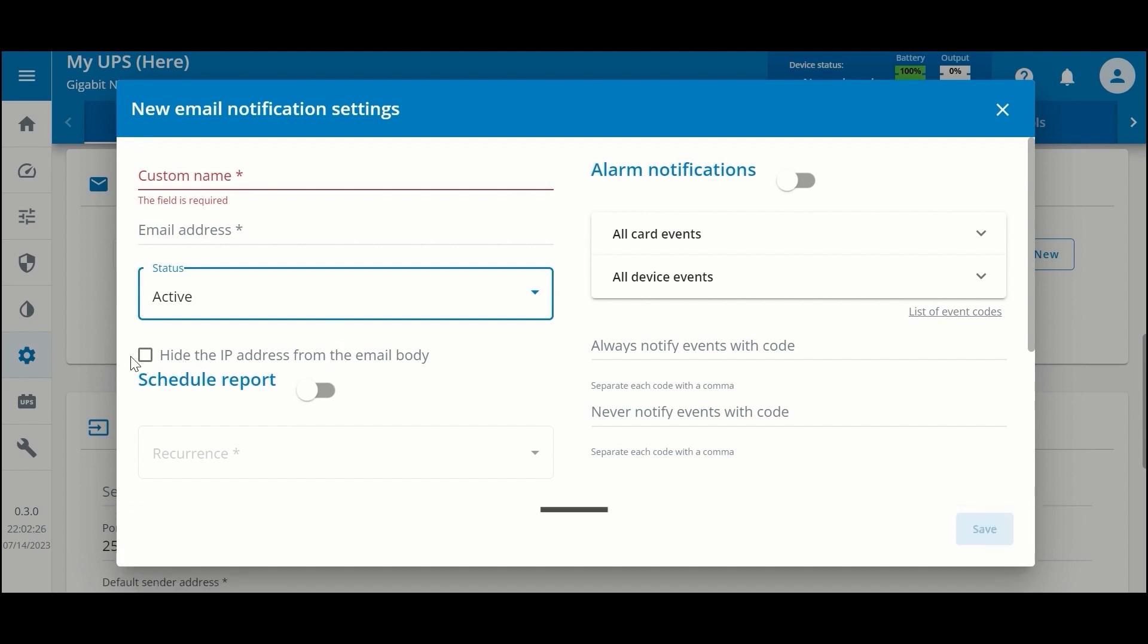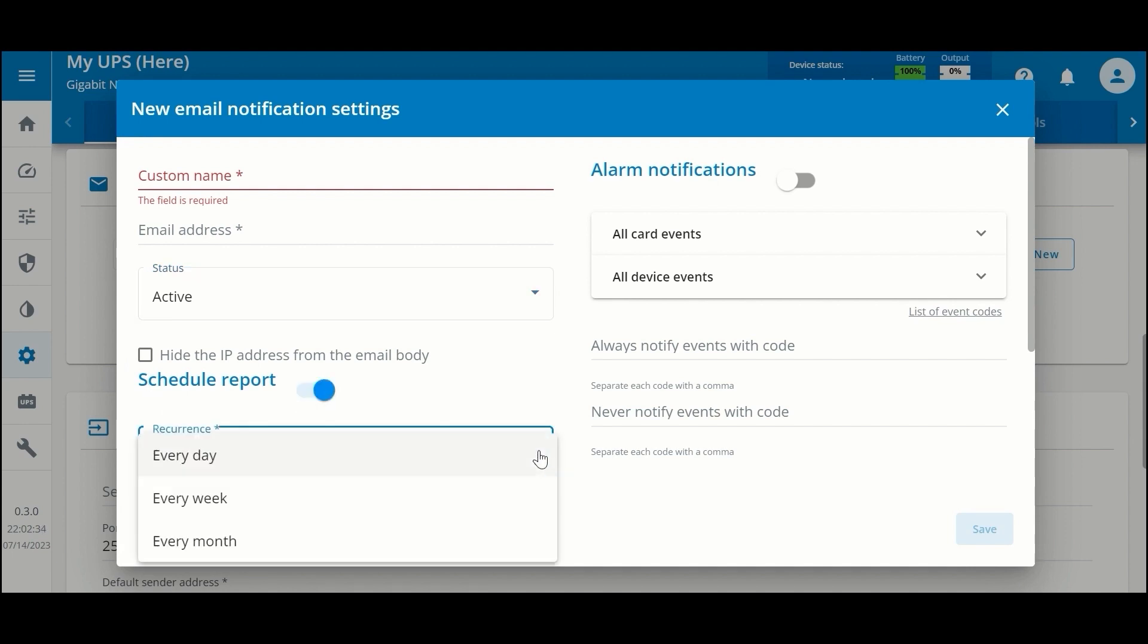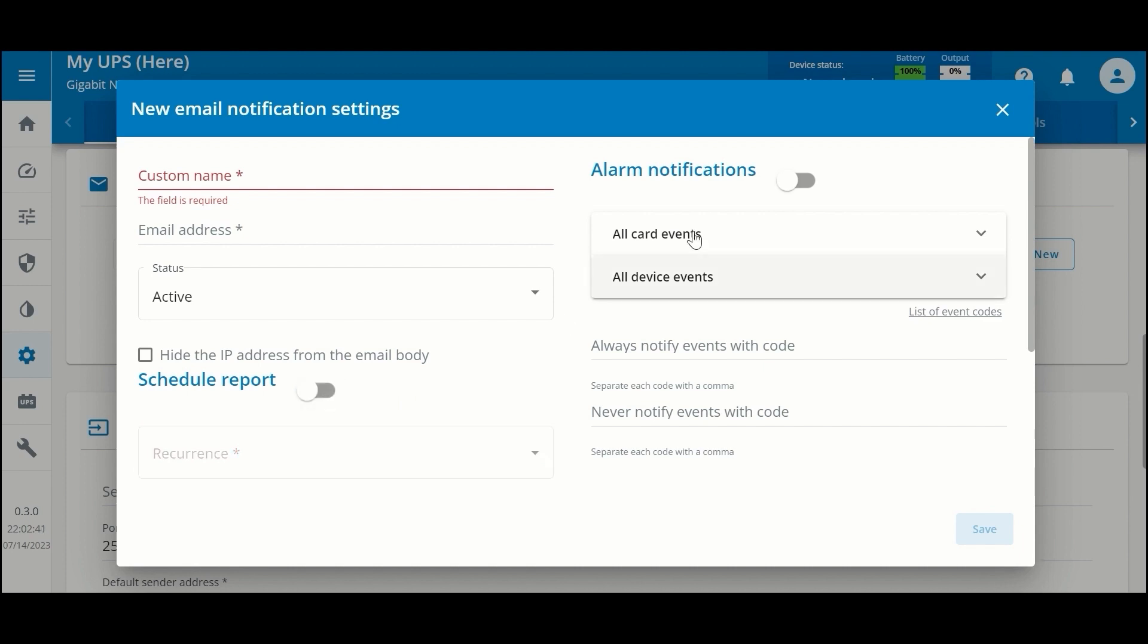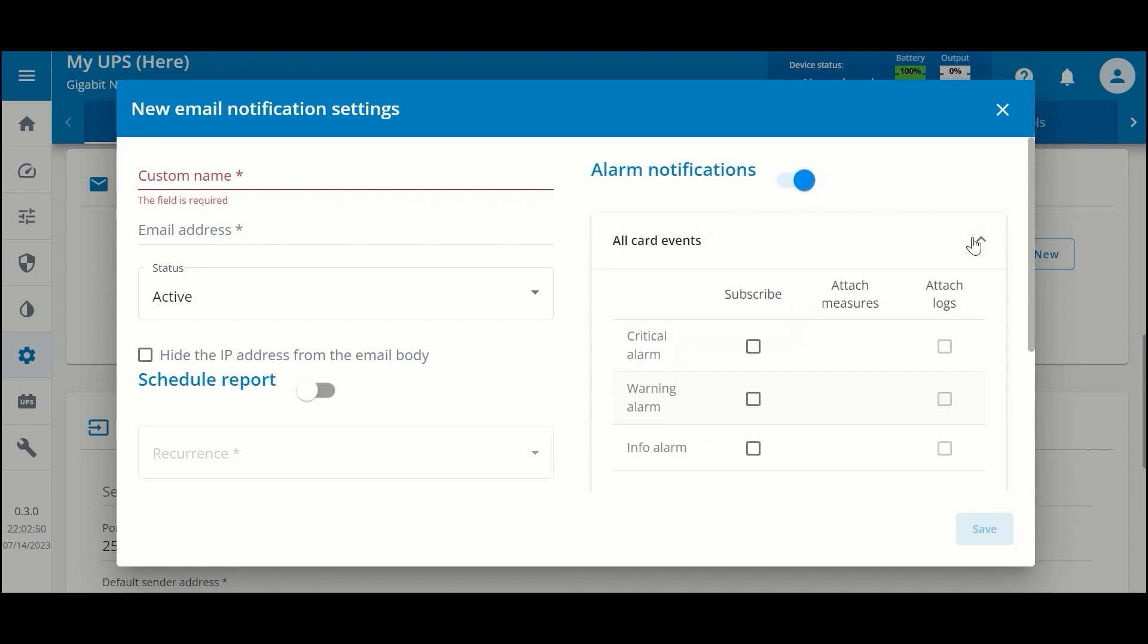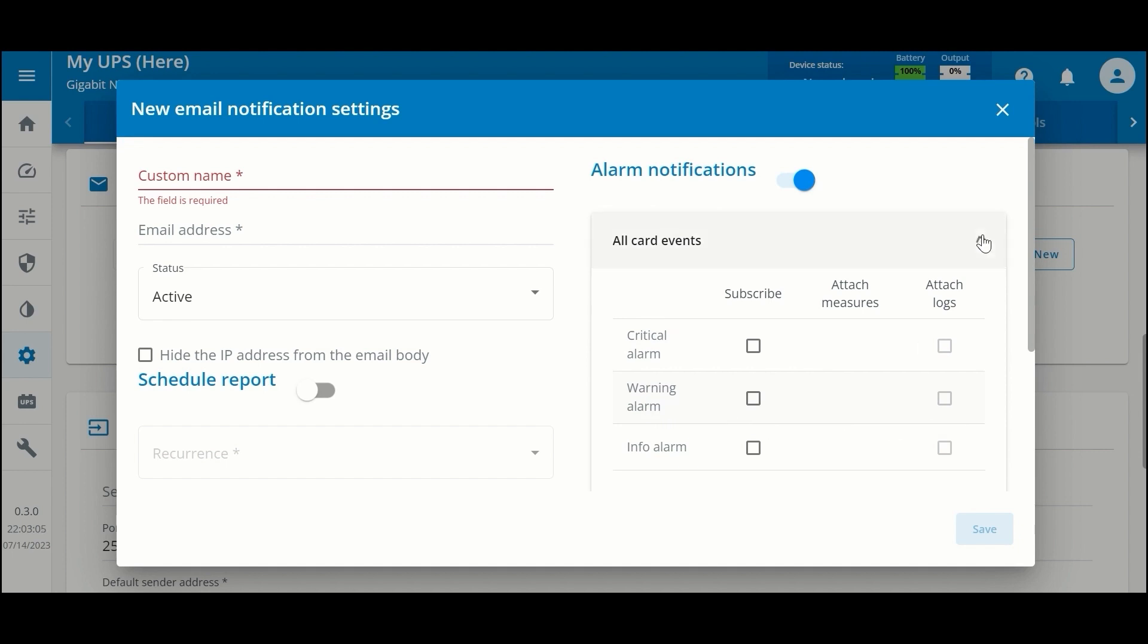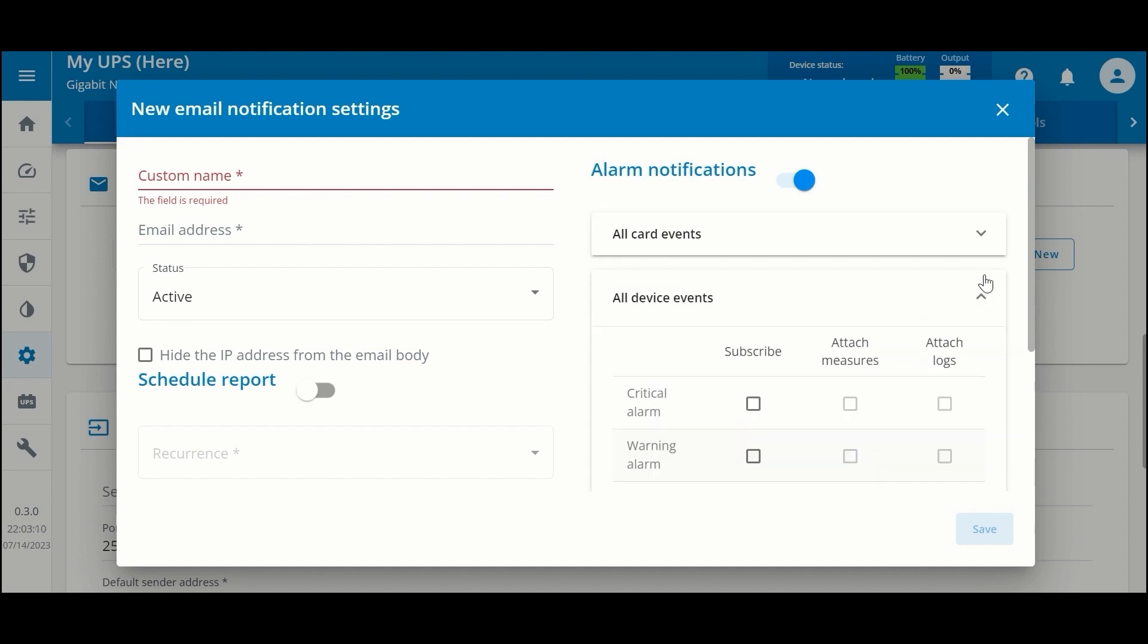You do have the option to hide your IP address from the email body and to schedule reports during certain recurrences—every day, every week, every month. If you enable alarm notifications, then you'll get an email every time there is an alarm, and you can subscribe to various criticalities of alarms such as informational, warning, and critical events. You can choose to attach logs, and these are separated by network card events and by UPS events.